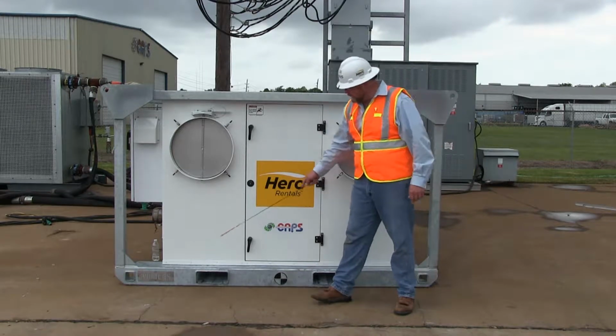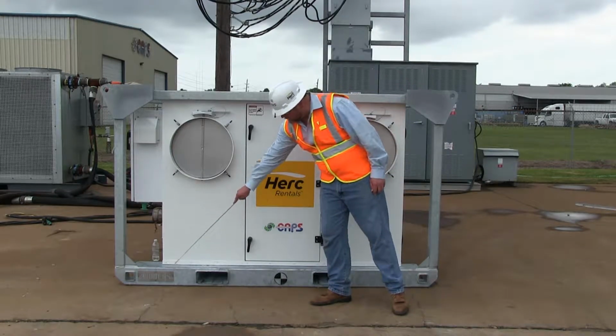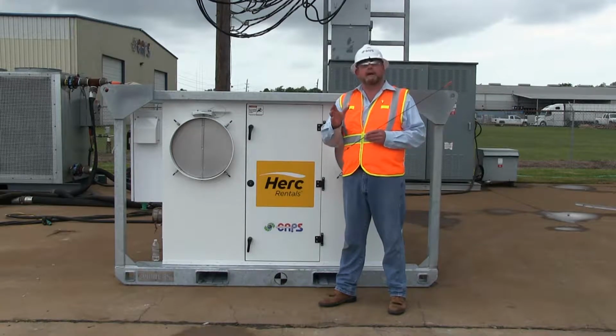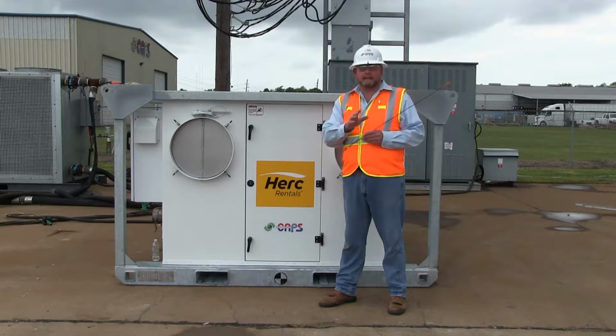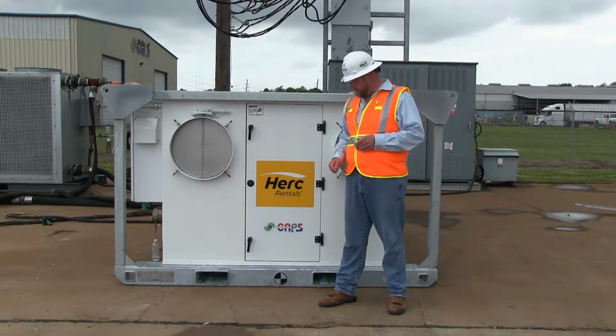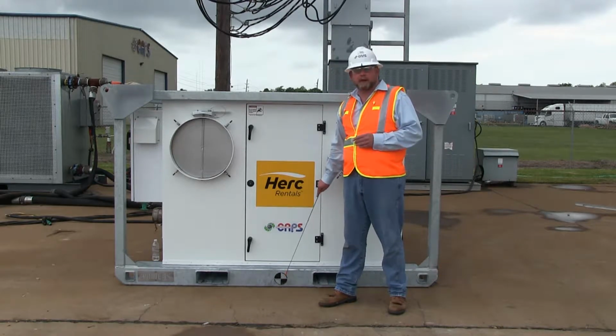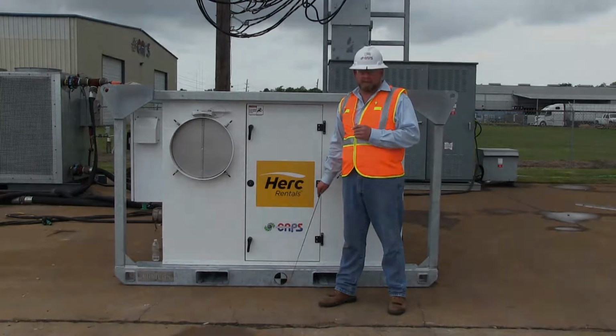And you always need to check the weight tag here at the bottom, which is one weighs 3,500 pounds, to verify that the forklift or the crane has the capacity to be able to move the unit. The center of gravity is clearly marked on both sides as well for rigging and for safety.